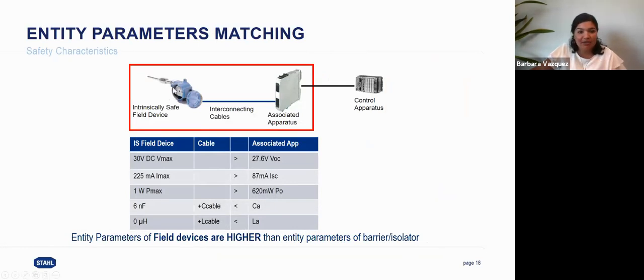The entity parameters of the field device are the maximum amount of energy the field device can receive and still be safe. So in this case, this device says I can receive up to 30 volts, up to 225 milliamps, up to 1 watt, and still be safe. It's still not spark, still not overheat.